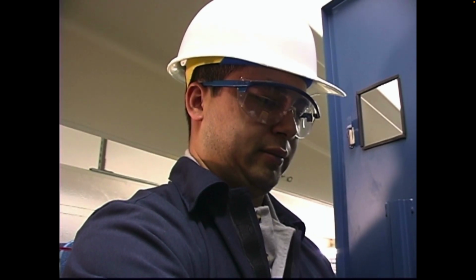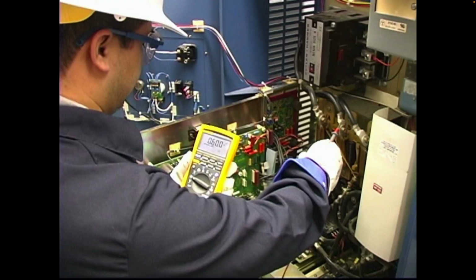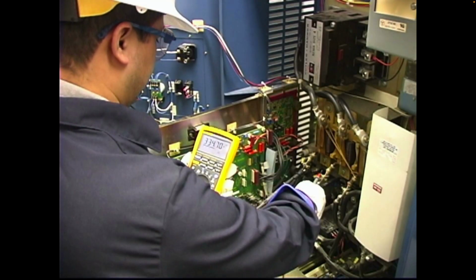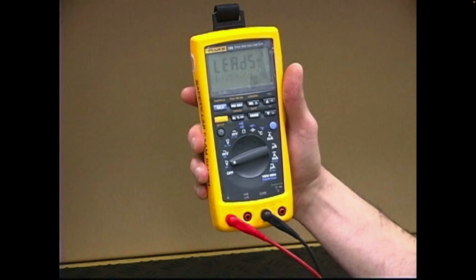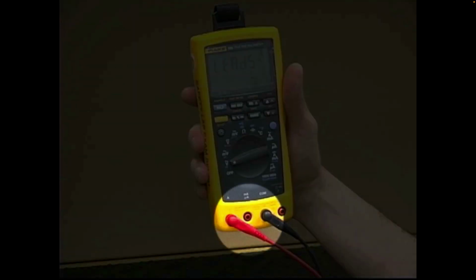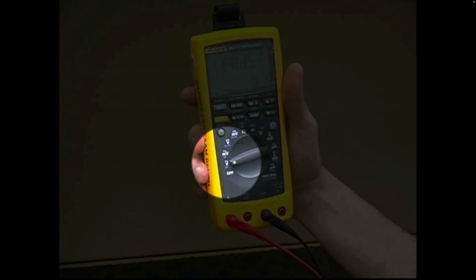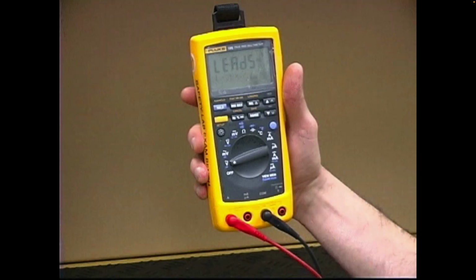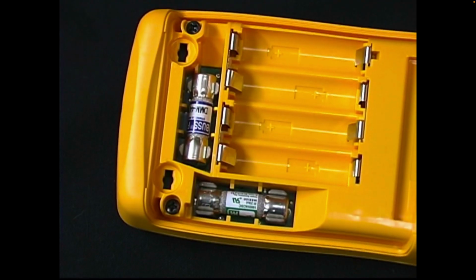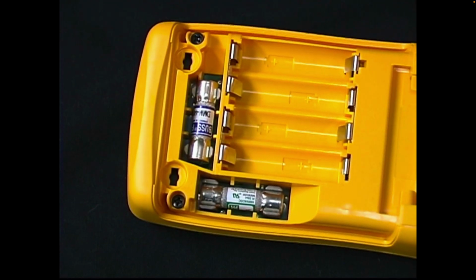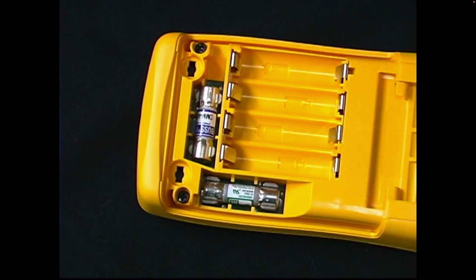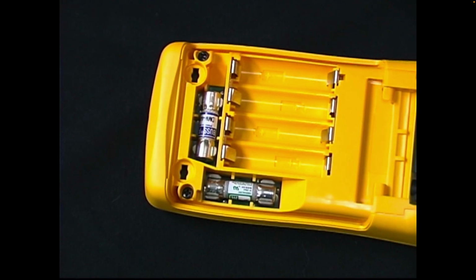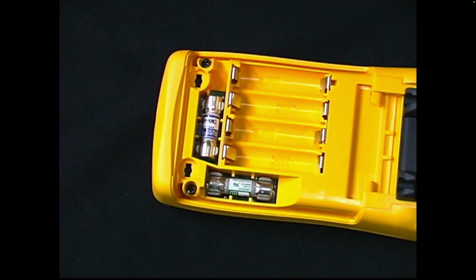Transients aren't the only source of arc flash hazard. In fact, one of the most common misuses of handheld multimeters can cause a similar chain of events. If the user leaves the leads in the amp's input terminals and then accidentally connects the meter leads across a voltage source, he has just created a short through the meter. That's why the amp's terminals must be protected by fuses. These fuses may be the only thing standing between that user and a potential disaster.